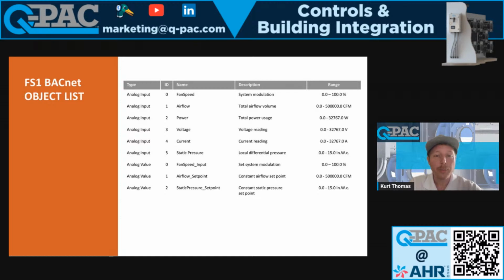We tell you what the power consumption is in watts, what the voltage is. It goes all the way up to 32,000. So if you ever see that, then you definitely have a bigger issue. But typically, it won't go above 480 or 500, right? Current reading. So we also tell you how much current is being drawn through our entire system. That's not just our fans, but that is right at the input of the control panel. We have a CT sensor there. So it'll take into account our power supply, and the PLC and any other smaller components that are drawing power.